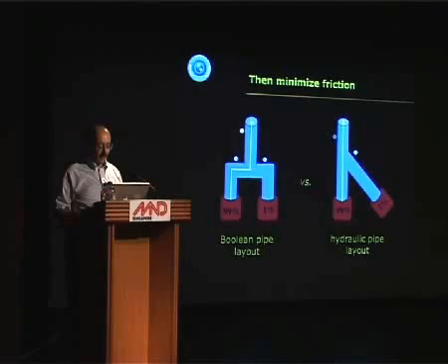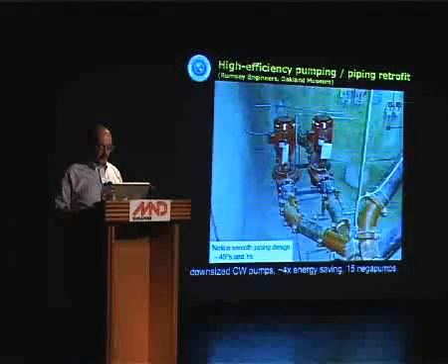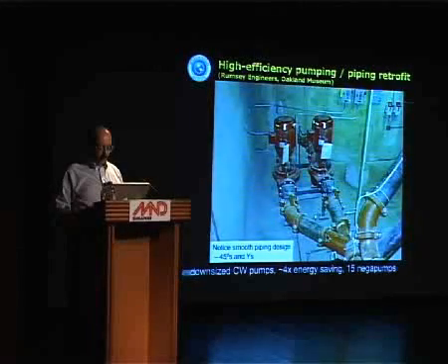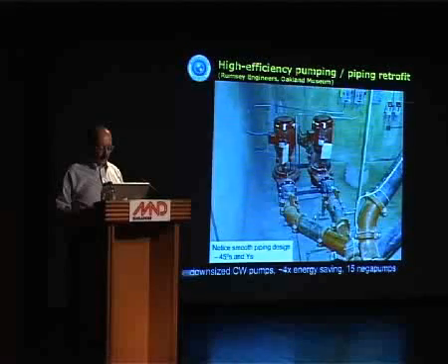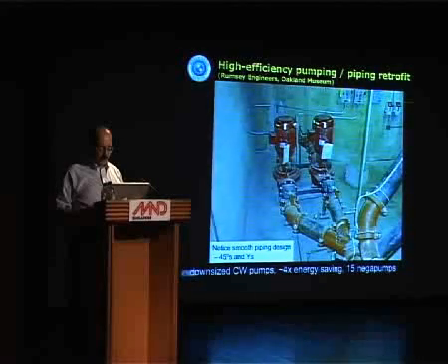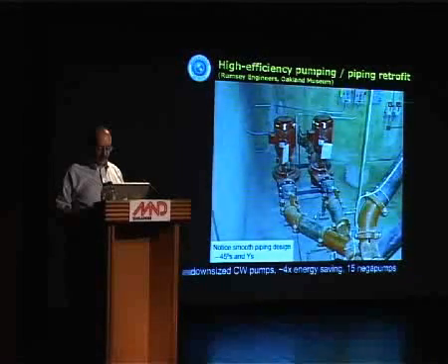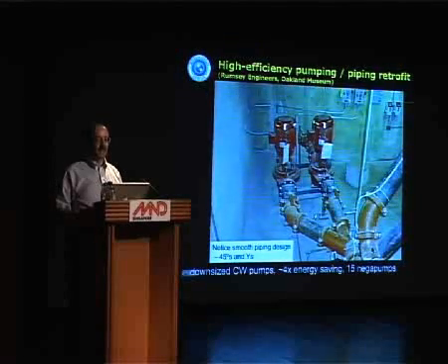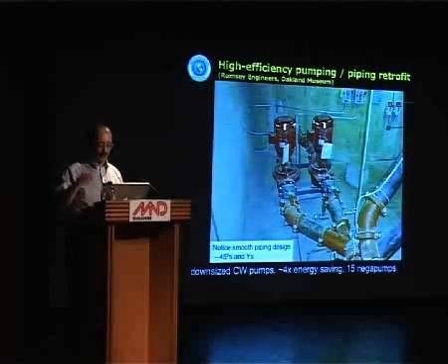It's different. But Peter Rumsey, a protege of Mr. Lee's, colleague of mine, did that as a retrofit and saved 3/4 of the energy in this condenser water system. Notice he has not just a Y joint, but a sweep bend with a pipe running diagonally through the air because he correctly instructed the pipe fitter to lay out the supply pipes as if they were drains. Drains, of course, with right angles will clog.